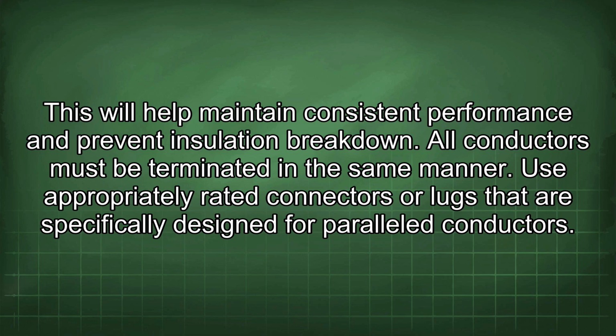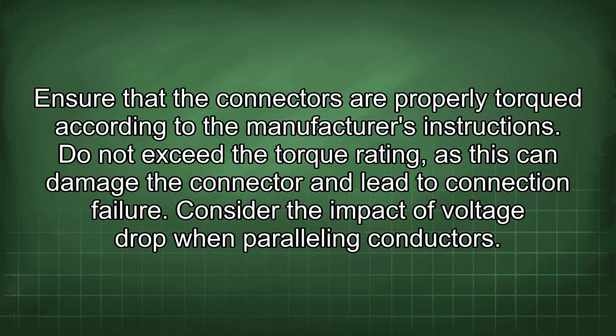All conductors must be terminated in the same manner. Use appropriately rated connectors or lugs that are specifically designed for paralleled conductors. Ensure that the connectors are properly torqued according to the manufacturer's instructions. Do not exceed the torque rating, as this can damage the connector and lead to connection failure.